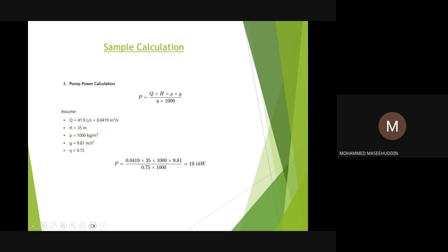And the power, of course, we have selected the pump based on the flow rate and the head. Now for the power required, if you remember the performance curve, it was showing everything. On top of the curve, you get the pump with the flow rate and head, and you select the pump model. And if you go to the bottom of the curve, you can select, based on the same duty conditions, the capacity of the motor required to run this pump efficiently. The same thing is also calculated in this way, the power required for the motor itself.